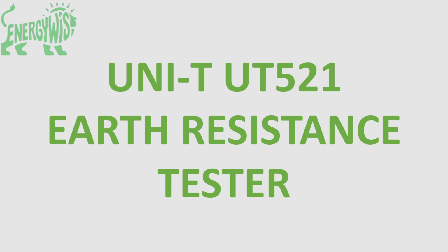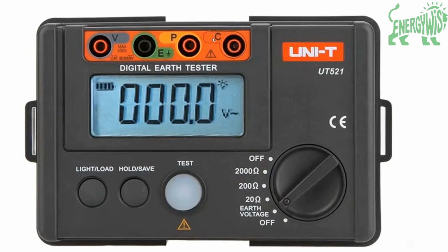We're going to see how we can measure earth resistance using the UT521. This is how it looks. It's the UT521 unit. Here we have a voltmeter probe terminal, another one for earthing, and the P and C terminals, which are spike terminals.